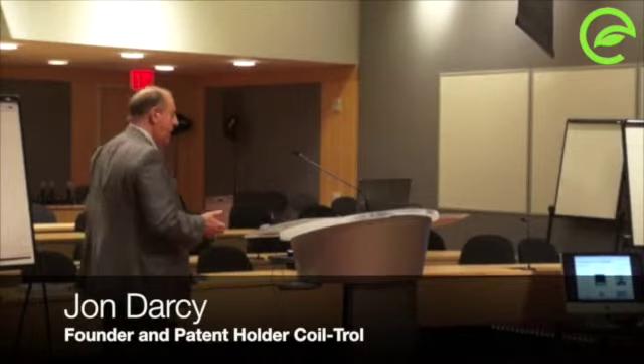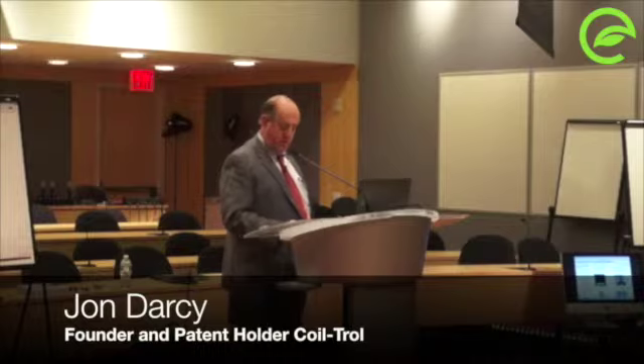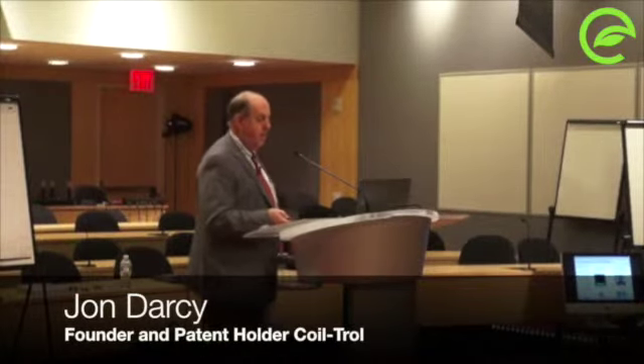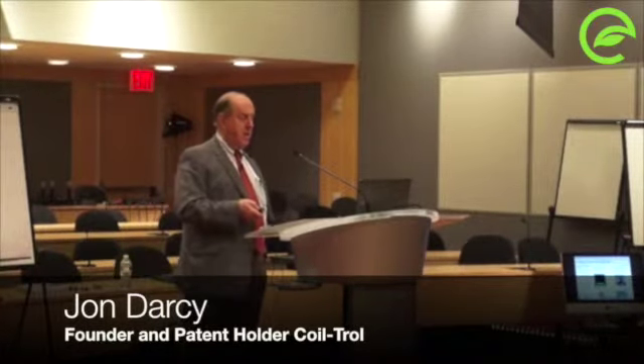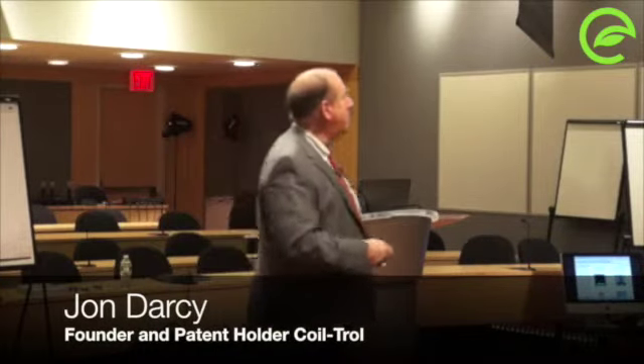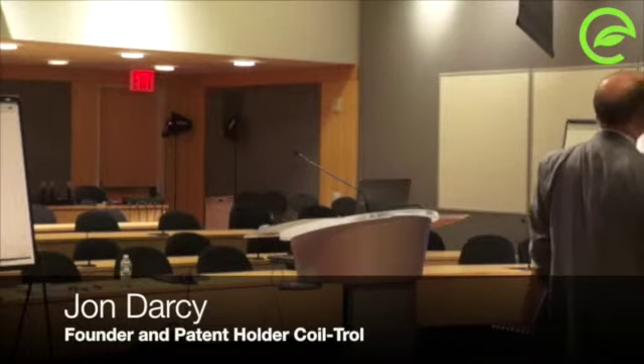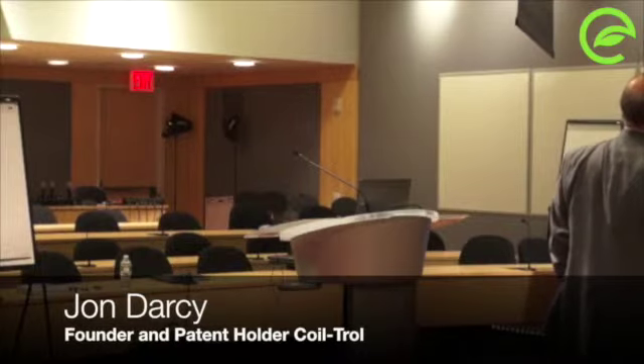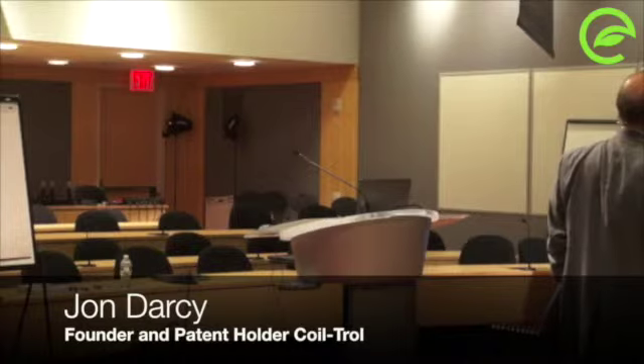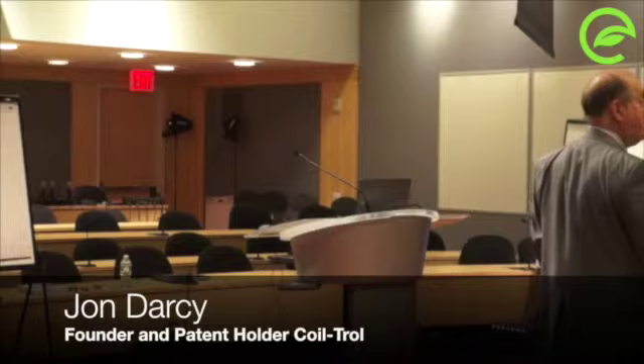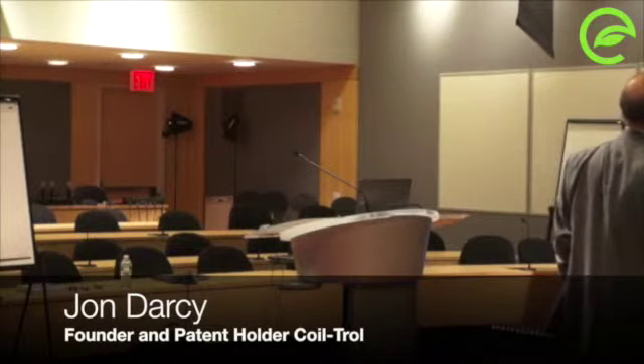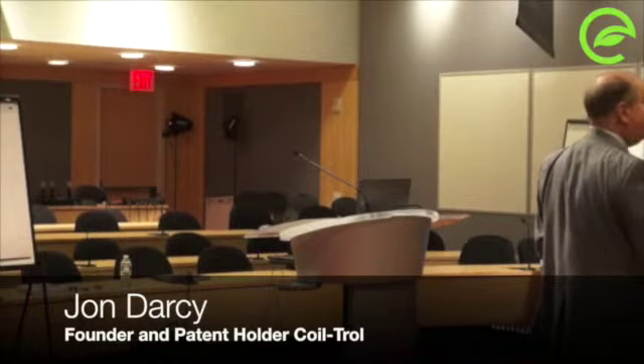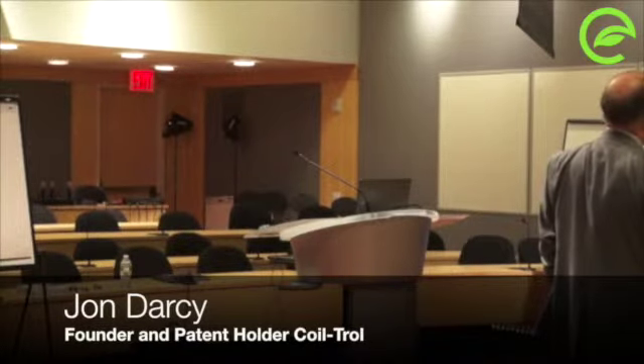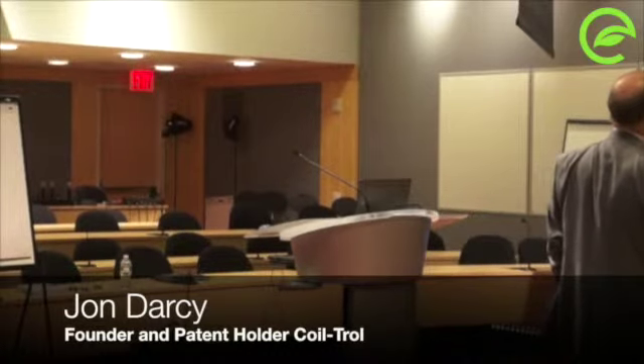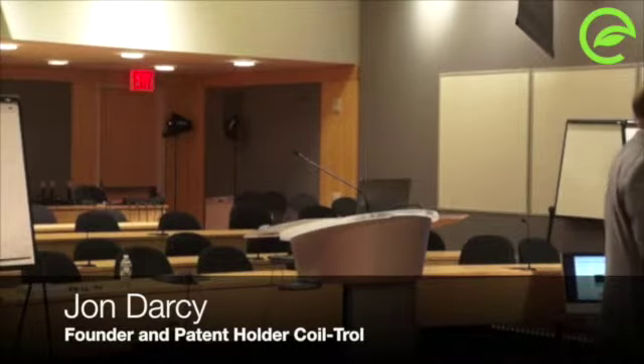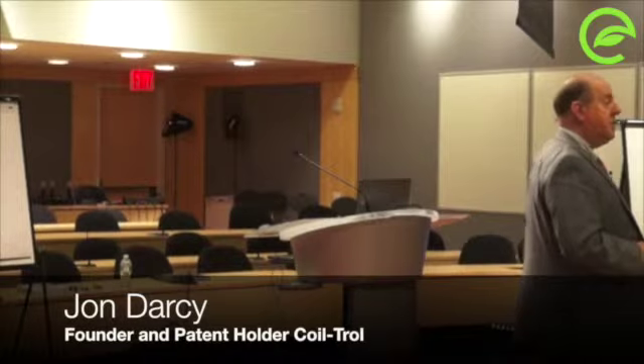Now, it also has some really neat other effects. There's a picture of a simple way of doing it. We measure return air temperature and humidity, and we calculate the grains. I like to look at the leaving water temperature and the supply water temperature, but that can come from the building automation system. It doesn't make any difference. Then we send a 4 to 20 milliamp signal to your building automation system. The only thing you need to buy is the pump and the check valve. I advise you to buy a few sensors, but you don't have to. And the functionality of this little box can be programmed into your building automation system, or we can supply a box that does it.